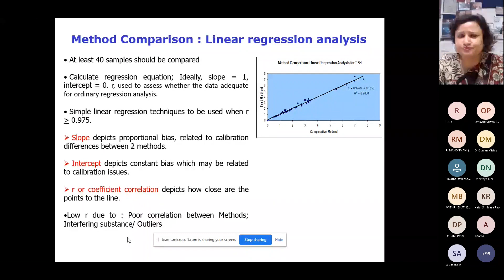And plotting the bias plot, ideally it should be 0, but you can see what bias is acceptable, and then you can study it. Then verification of precision. Precision is the closeness of agreement between independent test results obtained under the stipulated conditions, and is expressed in terms of imprecision, like standard deviation or coefficient of variation of the set of replicates.